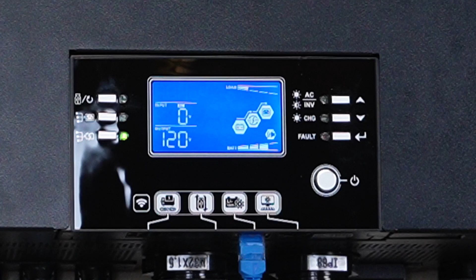Okay, so we're back to running the capacity test. The problem was, well, it wasn't a problem. I was able to change the battery type from Pylon in the inverter to user-defined, which allowed the setting to actually go down to 44 volts. I think it must have been set at 50 as low voltage cutoff. So now it's set at 44. So we'll continue with the test. Let's see where we are.